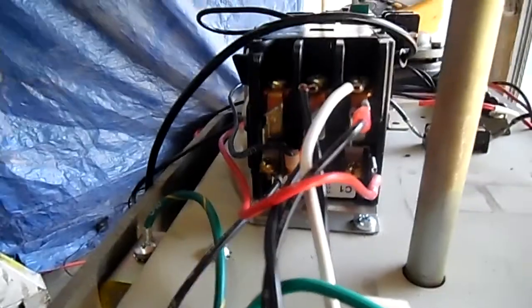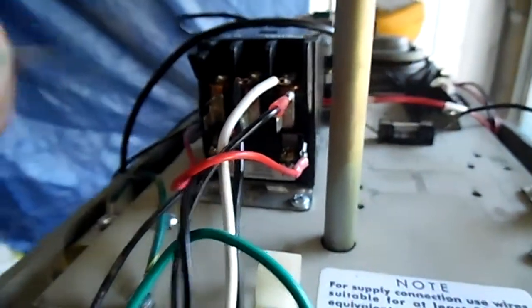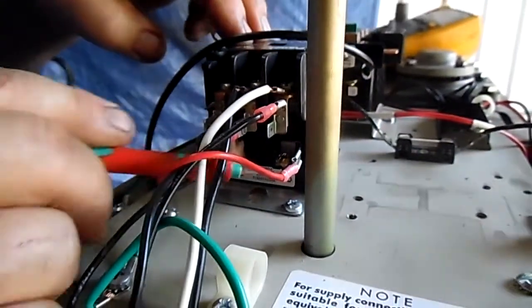and your switch is powering the other side through all the switches. If you want to make sure your coil is making contact, you could make a temporary jumper to here, plug the machine in, and it should pull in. That tells you your contactor coil is working. If that didn't close, your contactor is bad.